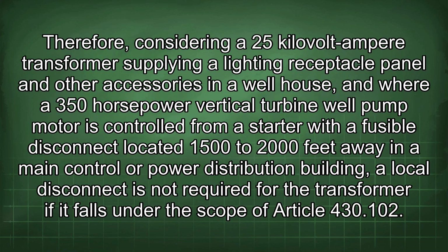Therefore, considering a 25 kilovolt-ampere transformer supplying a lighting receptacle panel and other accessories in a well house, and where a 350 horsepower vertical turbine well pump motor is controlled from a starter, with a fusible disconnect located 1,500 to 2,000 feet away in a main control or power distribution building, a local disconnect is not required for the transformer if it falls under the scope of Article 430.102.